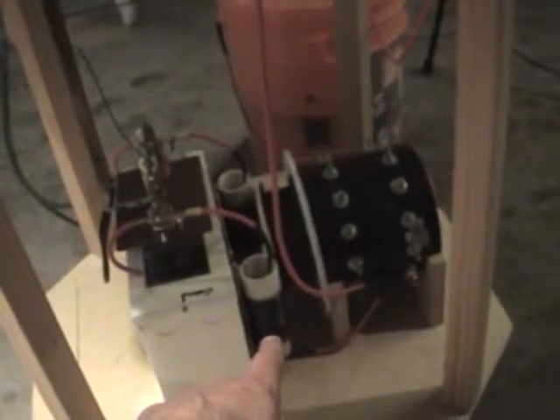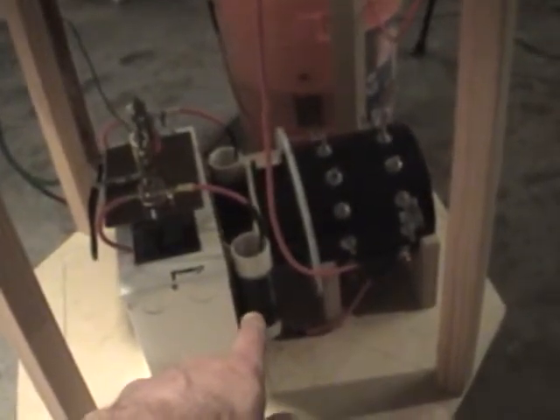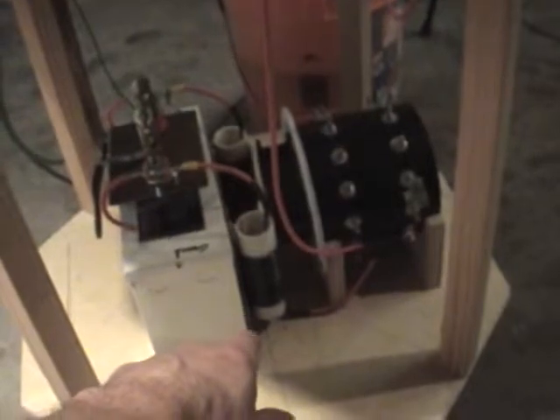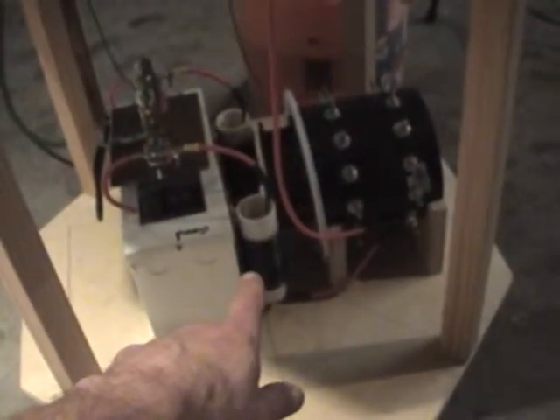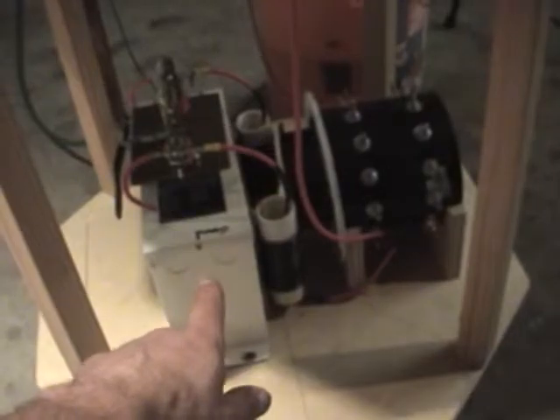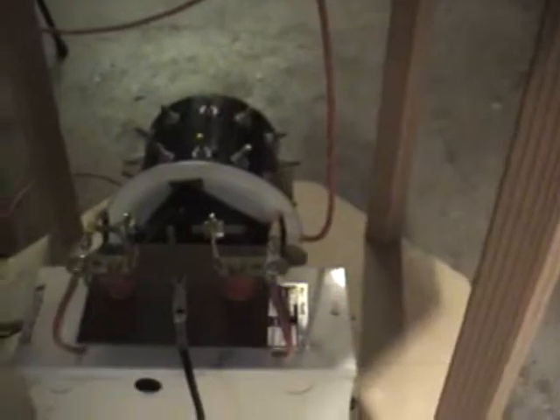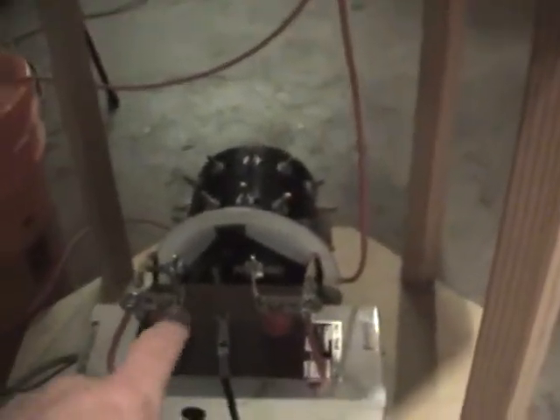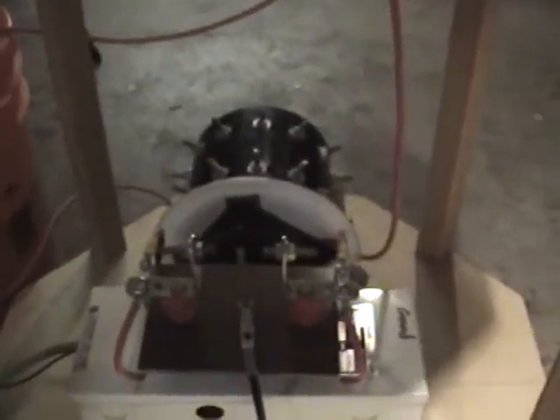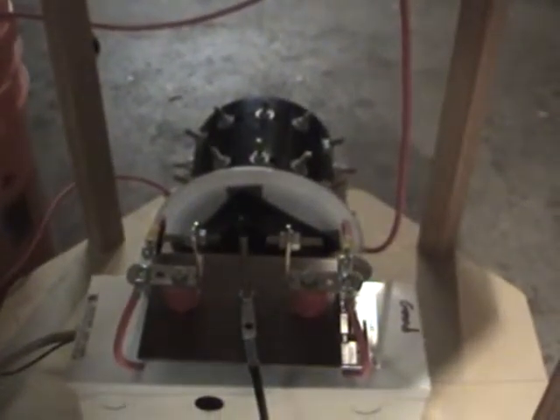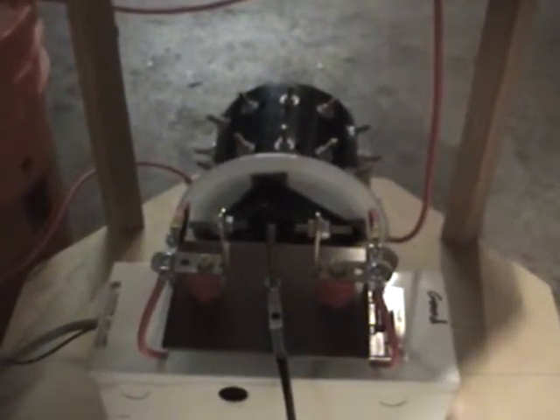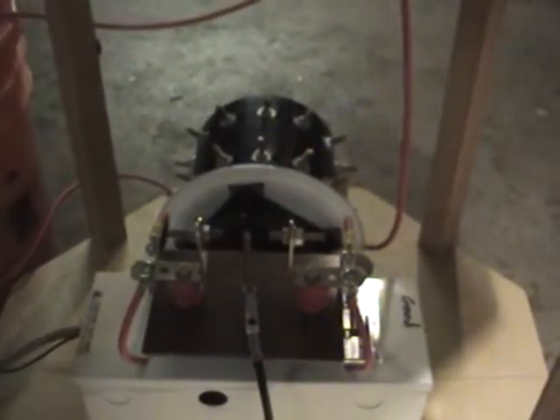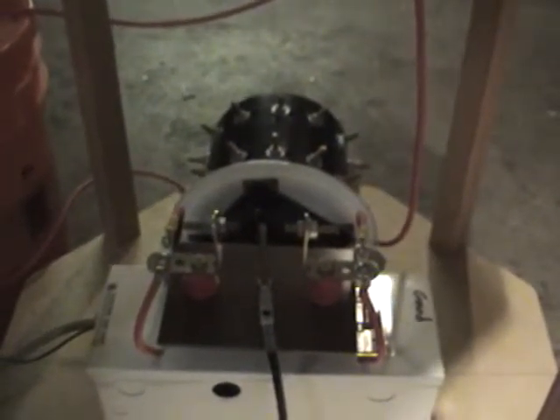Down here you see the neon sign transformer. Those are some inductors wound with some 26 gauge, I think it is, just for protection, to help protect the neon sign transformer. Same with this unit here. This unit here is the safety gap. That's the ground post in the middle and the two legs of the transformer. There's a gap there, so if it overvolts, too much voltage feedback, it'll arc across there and save the transformer.